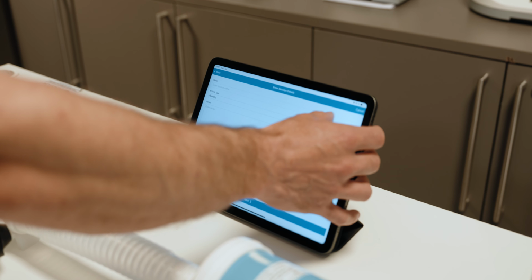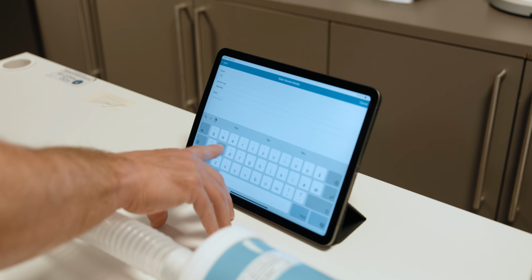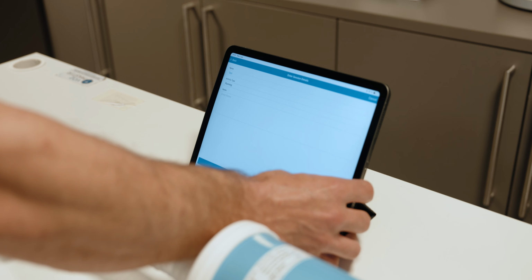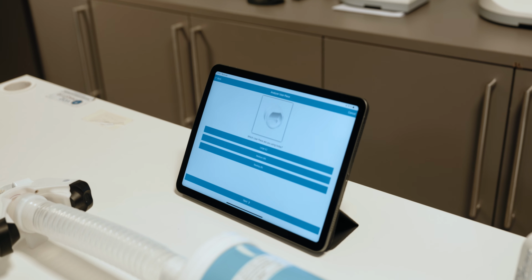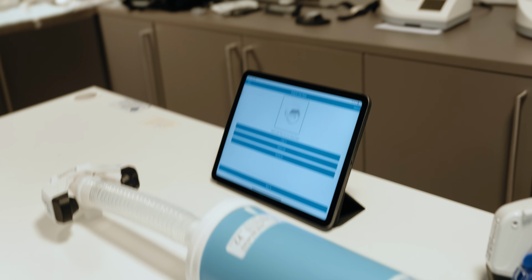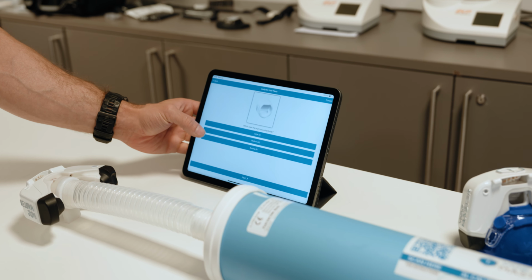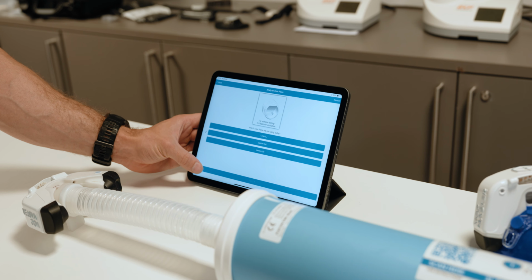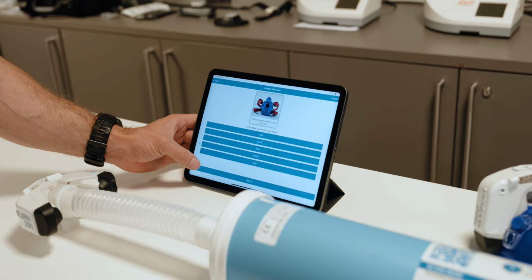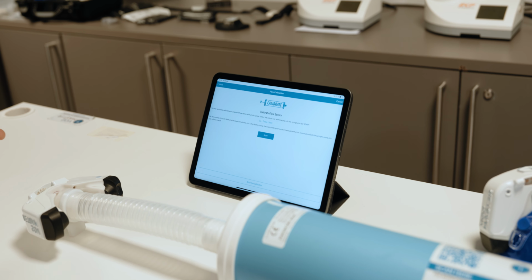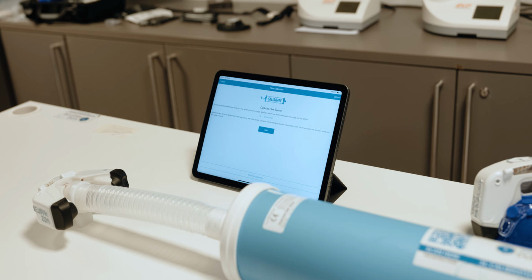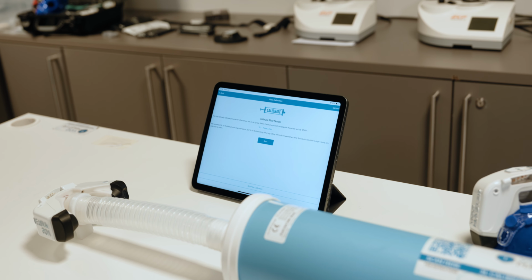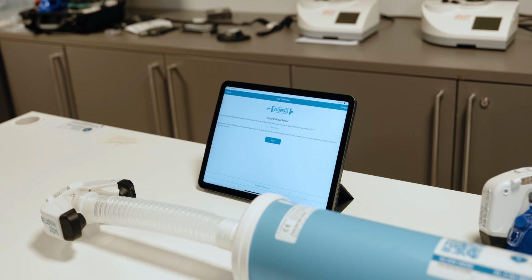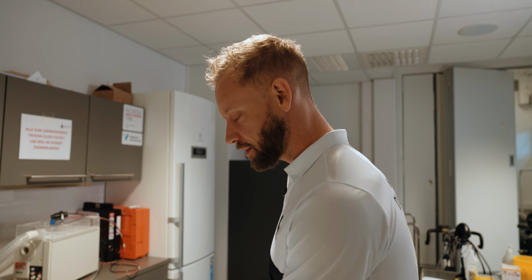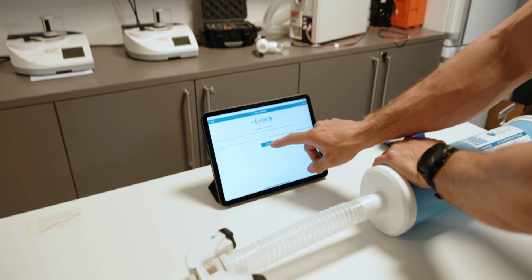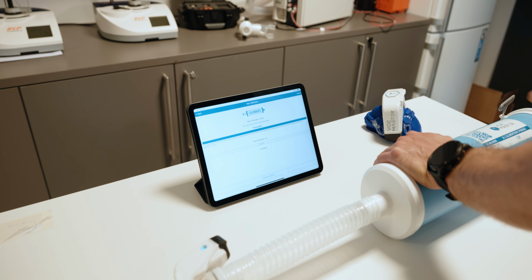I move to the next part. I will call this simply test. Next. And here again, you will be prompted to choose the correct user piece size, medium mask size. Next. And now we're ready to watch the metronome. For this part of the calibration, we simply have to follow the metronome when we press start. Okay, so let's start the calibration. We need 10 validated pumps in order to complete the calibration.